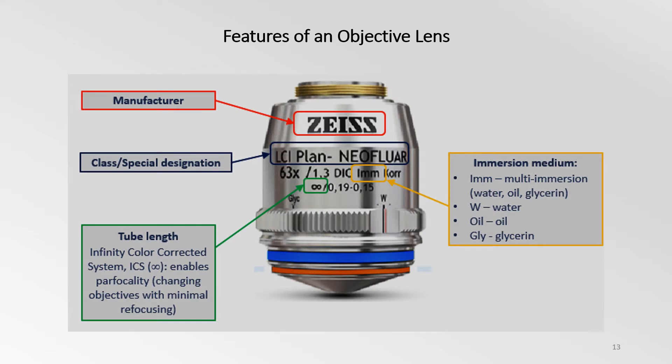There are a number of markings on the barrel of a microscope objective lens that contain the specifications necessary to determine what the objective is designed for. These include the manufacturer, the class or special designation, which indicates the optical corrections offered by the objective. The infinity mark inscribed on the objective refers to an infinity corrected objective, which allows the insertion of optical components in the microscope system without affecting focusing.